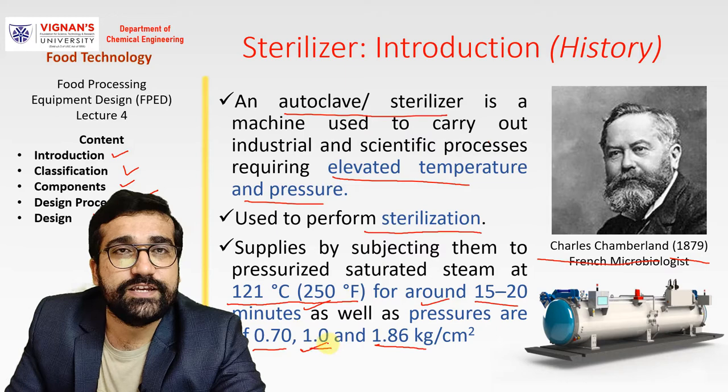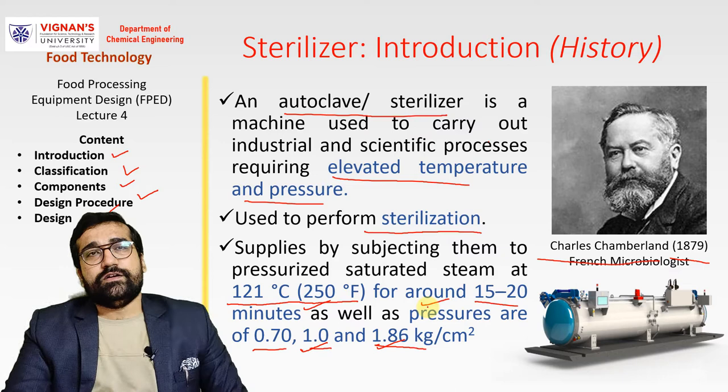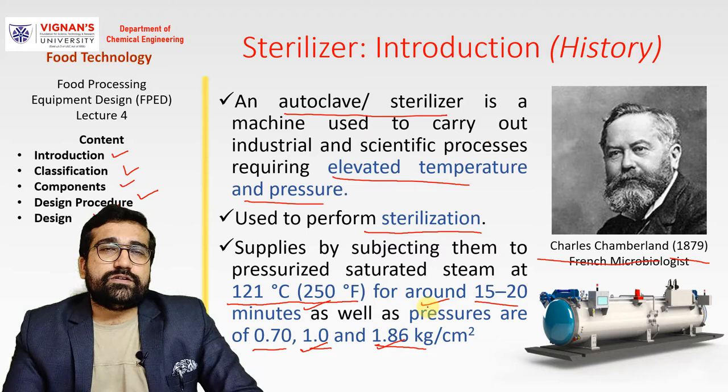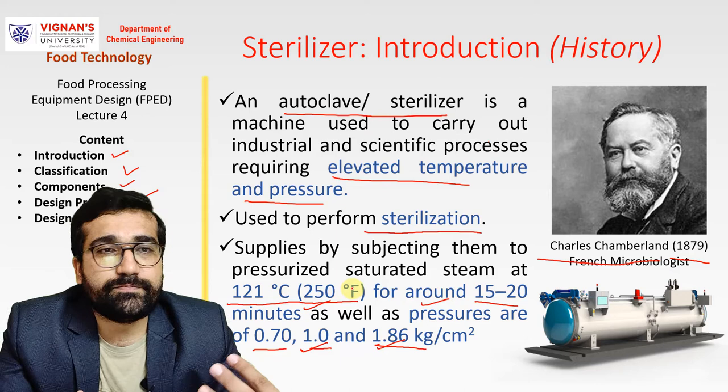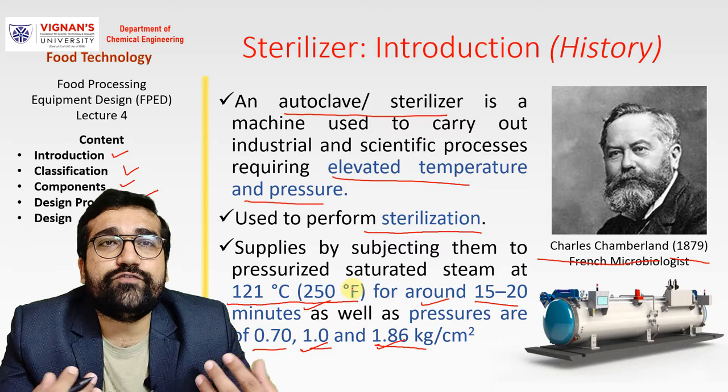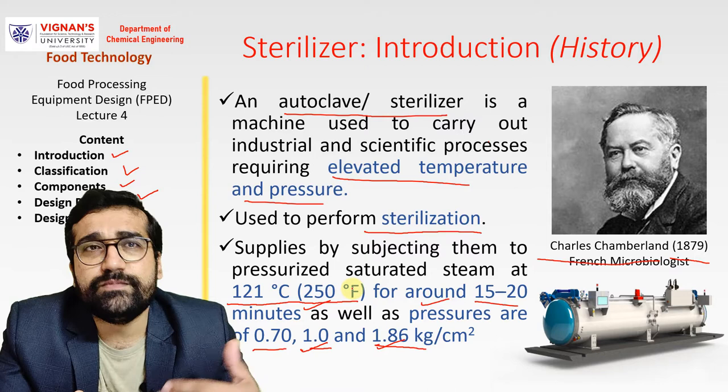Most of the sterilizers are steam based sterilizers. So why do we use steam based sterilizers? As we know, steam has higher kinetic energy compared to other media, like when we supply direct heat. In the steam there is a high amount of kinetic energy which will denature the protein of the microorganism at a much faster rate.